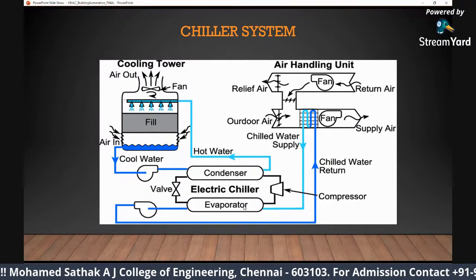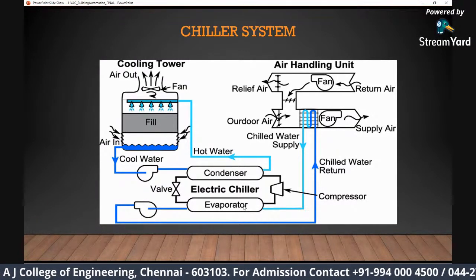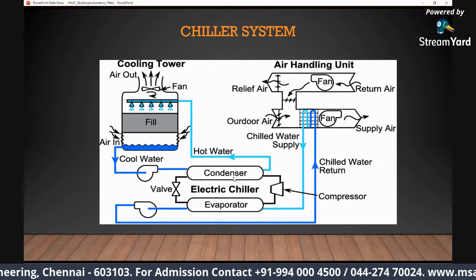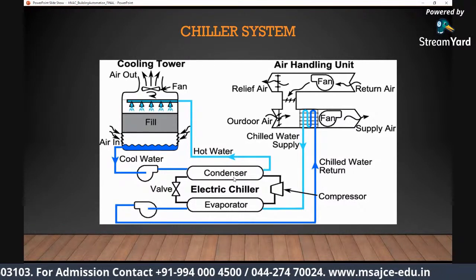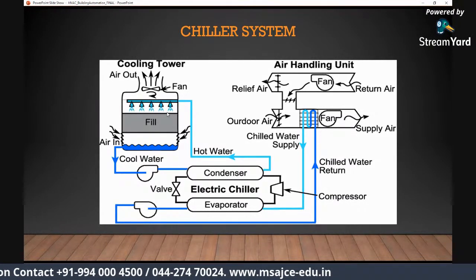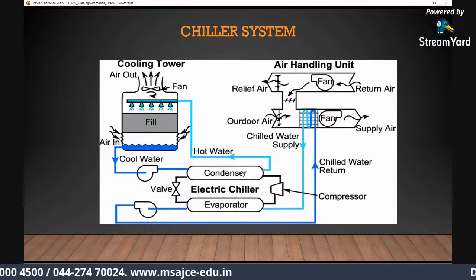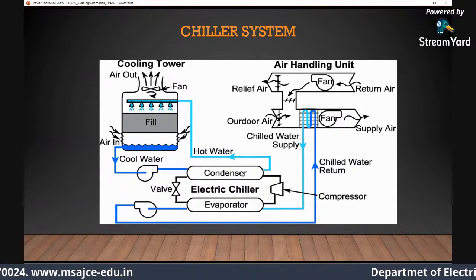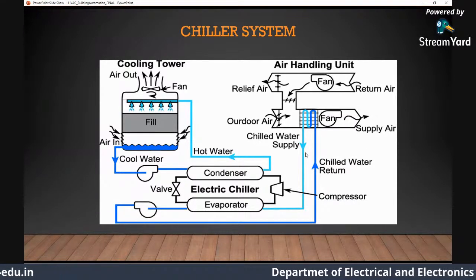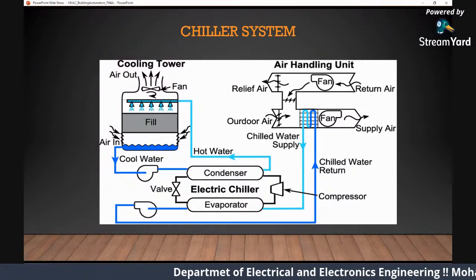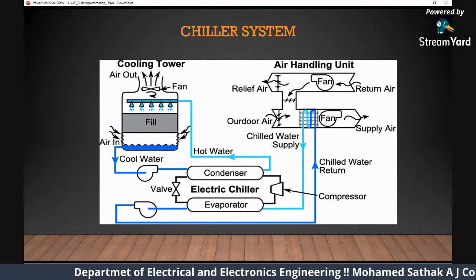Now this refrigerant, once it cools the chilled water supply which goes to the building, gets heated up. Now that again needs to be cooled. That is taken care of by the condenser. And again, the water from the cooling tower will cool the refrigerant in the condenser part. Now, this is a whole complicated operation. So if you're not getting any point, let me know. I'll try to brief on it again.